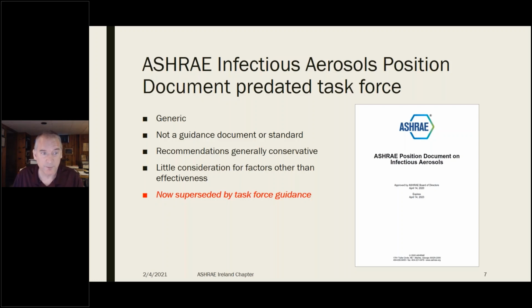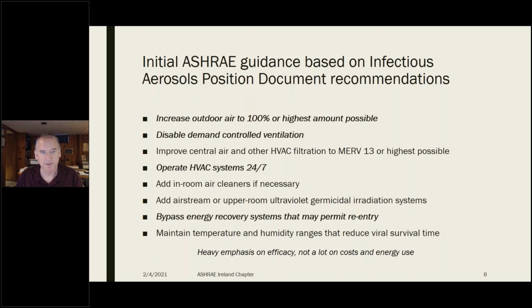I want to point out that it's generic. It was not written as a guidance document or a standard, and it talks about measures that can be effective, but it's generally conservative and doesn't consider things like comfort, energy use, or cost. If you're still referring to it, now would be a good time to stop, because it's not really ASHRAE's current guidance, and we're already in the process of revising this document based on everything we've learned during the pandemic.